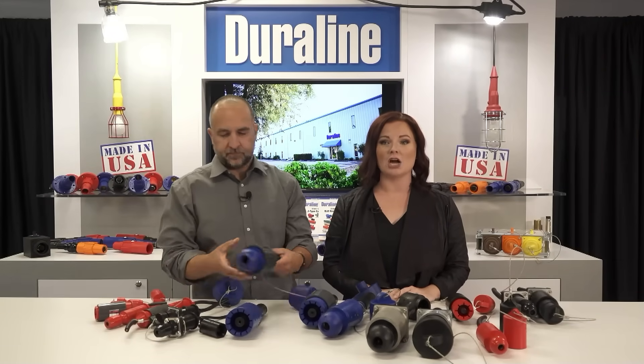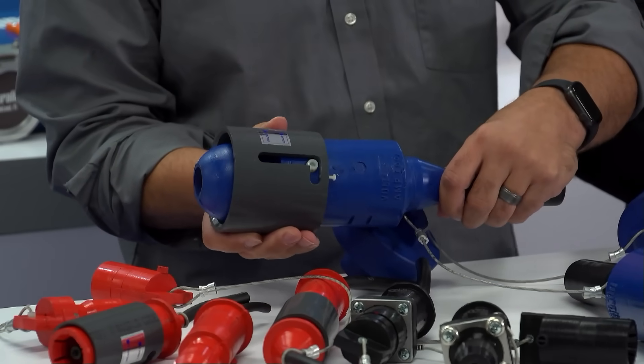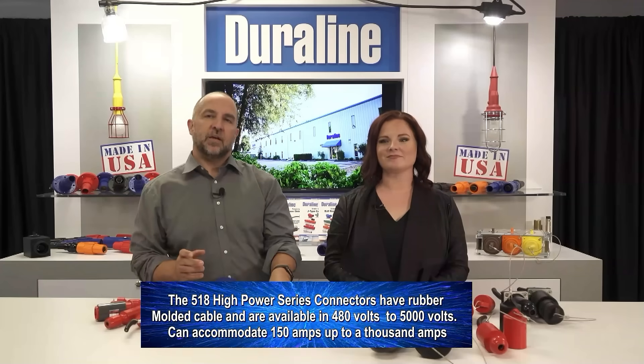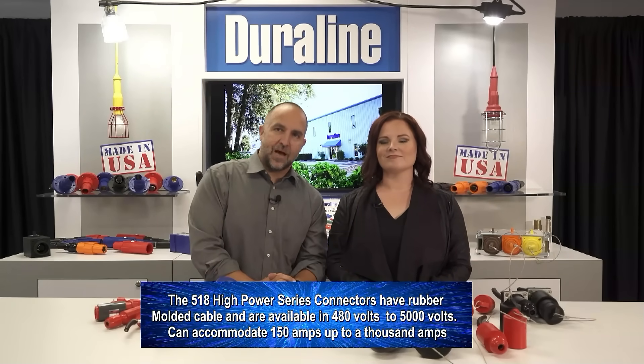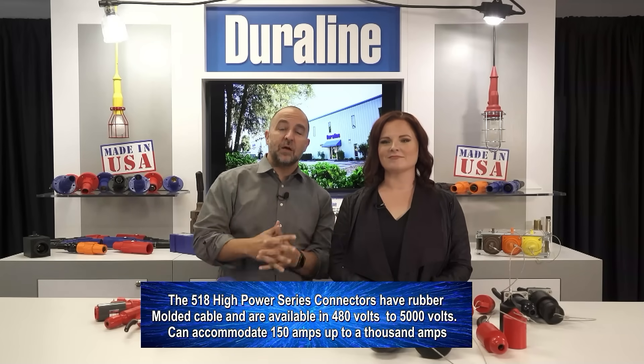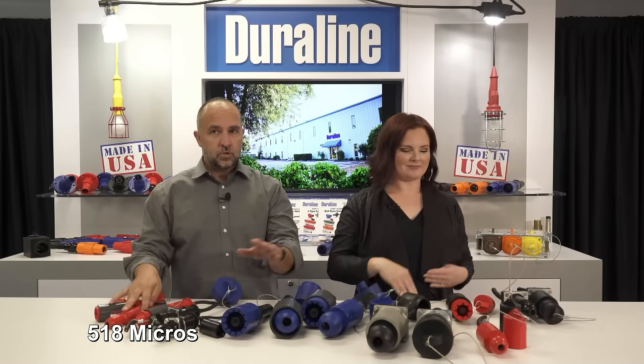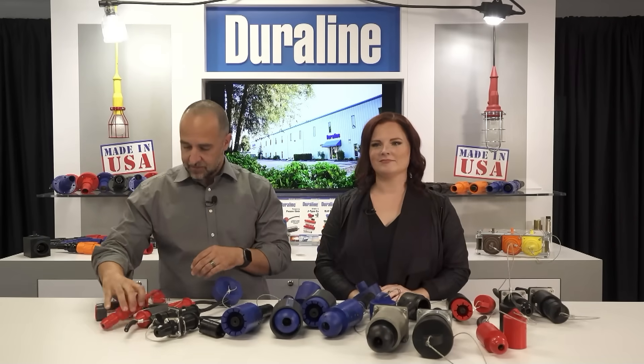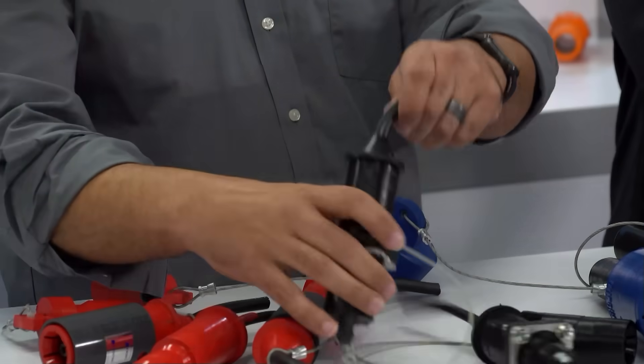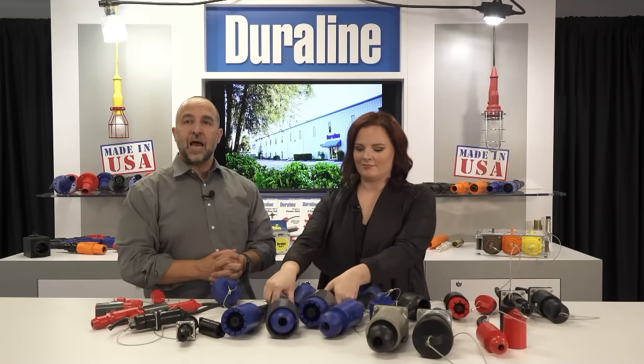There is no cam or keyway to line up, and there are no polarizing positions or twisted cables to worry about. When engaged, the locking ring provides positive locking force while allowing free rotation, even with rigid cables. The 518 high-power series connectors are rubber-molded to cable and are available in 480 volts to 5,000 volts and can accommodate 150 amps up to 1,000 amps. There are three different series in this family: 518-micros, juniors, and seniors, available as in-lines and receptacles.